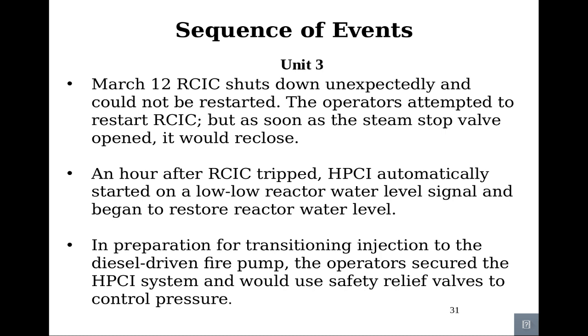Unit 3. On March 12th, reactor core isolation cooling shuts down unexpectedly and cannot be restarted. The operators attempt to restart RCIC, but as soon as the steam stop valve is opened, it would reclose. After an hour of losing RCIC, high-pressure coolant injection automatically started on a low reactor water level signal and began to restore reactor water level. In preparation for transitioning injection to the diesel-driven fire pump, the operators secured the high-pressure coolant injection system and would use safety relief valves to control pressure.